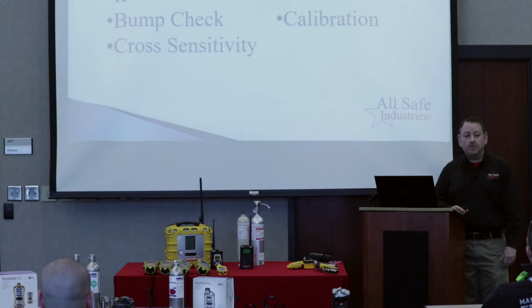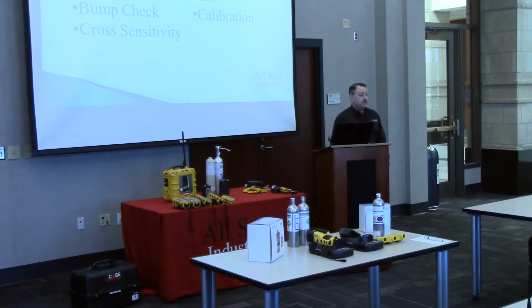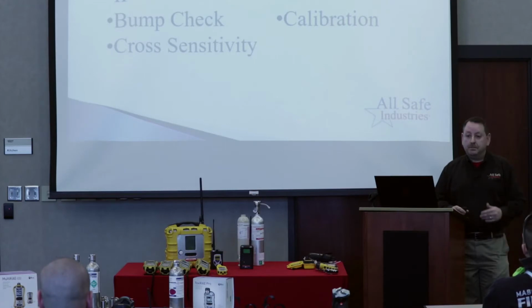And then who's heard of the term bump check? Is that a familiar term? See a few heads going up and down. A bump check is simply putting gas on the instrument and watching the sensors respond. There's really no better way for you to know that the equipment is working properly than to hit it with some gas, watch the sensors react, then you take the gas off and the sensors go back down to zero. Now you know that that meter is going to work right when you're using it on the job or in a confined space or wherever you might be using the gas detection.